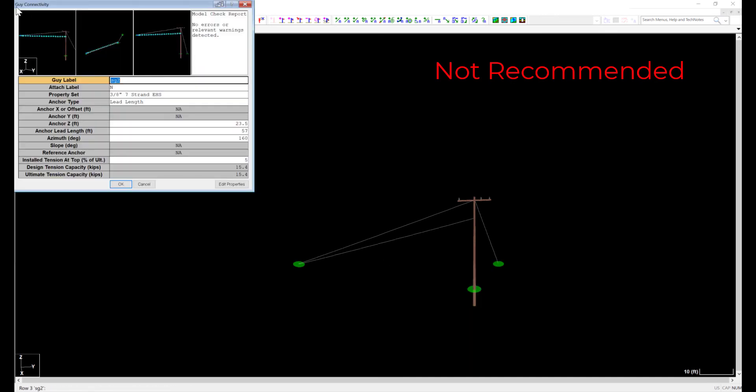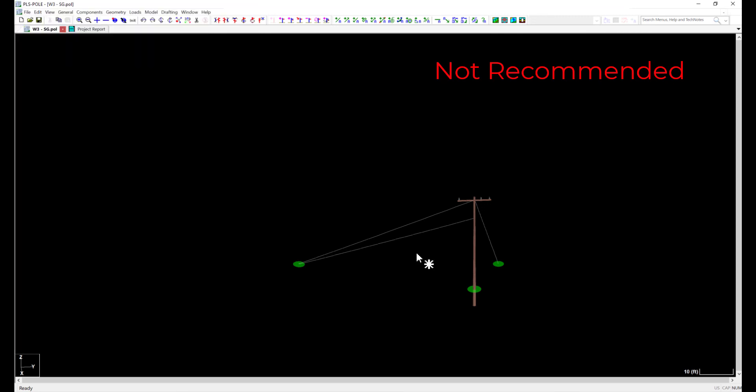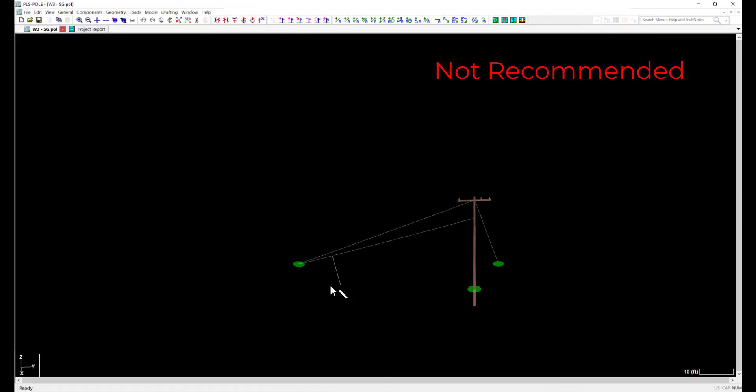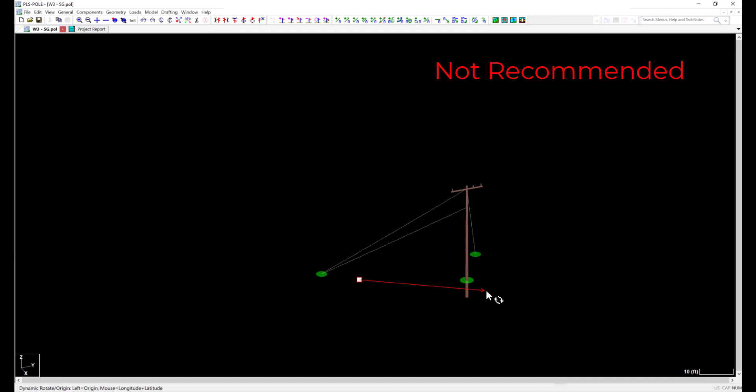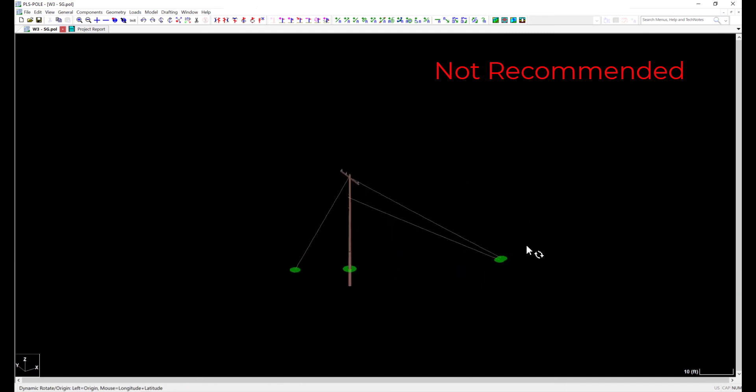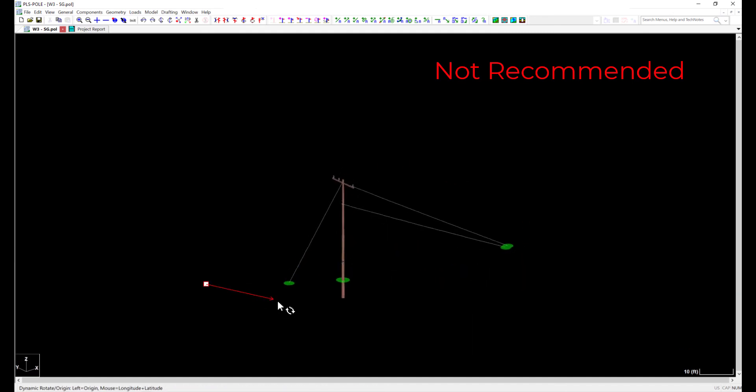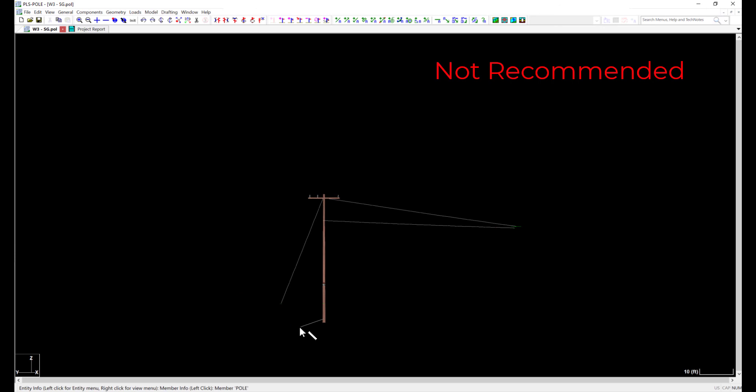In my example of this modeling technique, you can see that the down guys go off into space. If I were to add this to PLS-CADD, you would see that my guys mimic span guys. This can be fine if you are not concerned with the strength of the stub pole and assume that the stub pole is infinitely stiff, which will be less conservative for a conductor carrying pole analysis.